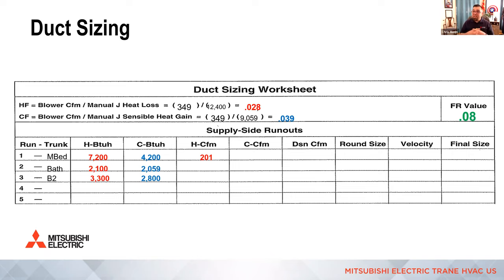Now, the way duct design and layout works, it's recommended 200 CFM or more. You split those runs into two because you have a big area and you want to spread that air around for that particular space. For this example, I'm just going to keep it simple and keep it as one run. But if I was doing this for a house in actual design, I might split this up into two 100 CFM runs in that example.